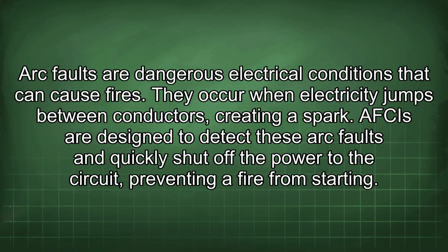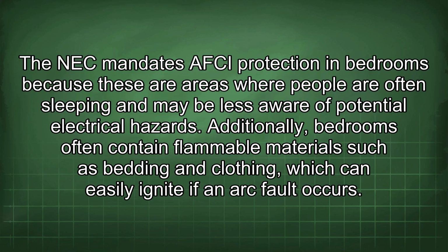Arc faults are dangerous electrical conditions that can cause fires. They occur when electricity jumps between conductors, creating a spark. AFCIs are designed to detect these arc faults and quickly shut off the power to the circuit, preventing a fire from starting. The NEC mandates AFCI protection in bedrooms because these are areas where people are often sleeping and may be less aware of potential electrical hazards. Additionally, bedrooms often contain flammable materials such as bedding and clothing, which can easily ignite if an arc fault occurs.